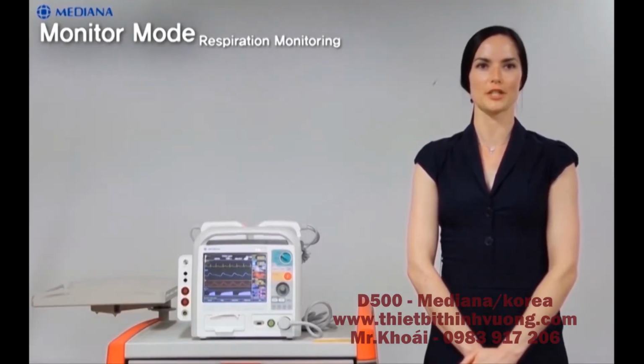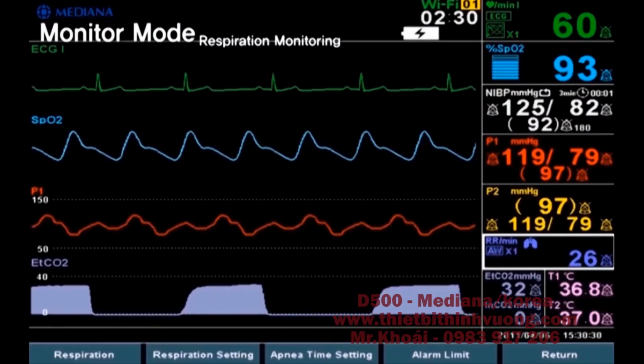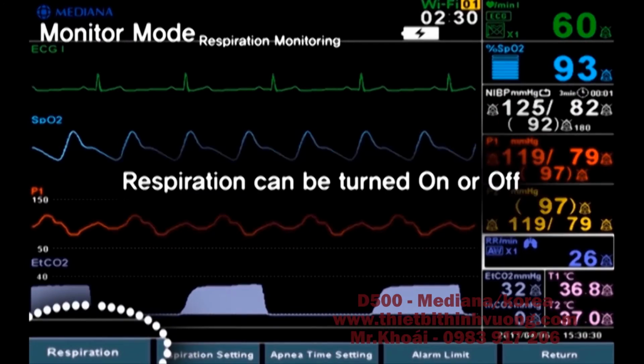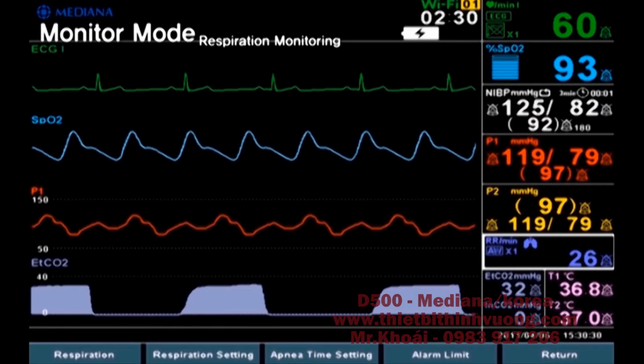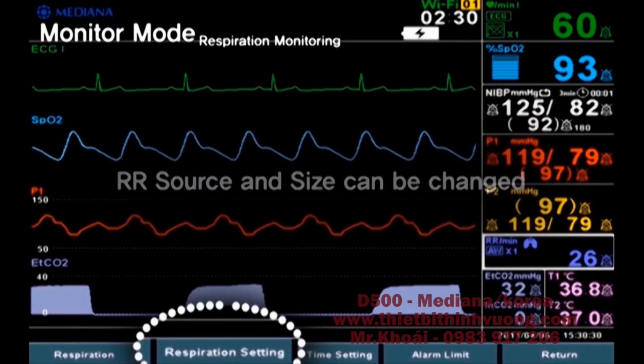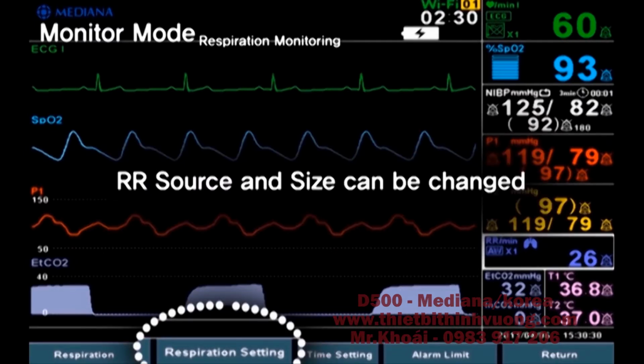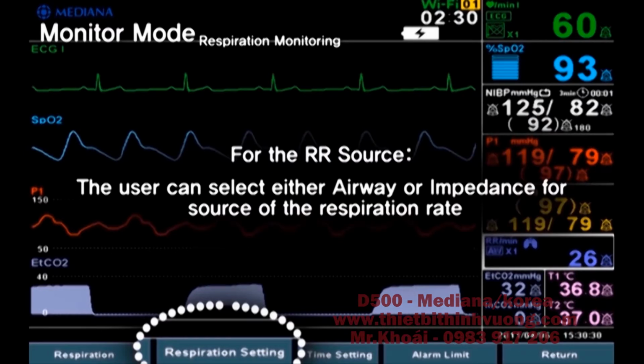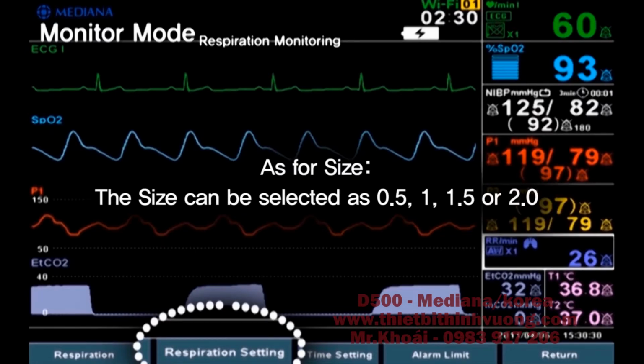Let's see the respiration monitoring menu. Number 1, respiration. Respiration can be turned on or off. Number 2, respiration setting. The respiration rate and size can be changed. For the respiration rate, the user can select either airway or impedance as the source of the respiration rate. As for size, the size can be selected as 0.5, 1, 1.5, or 2.0.